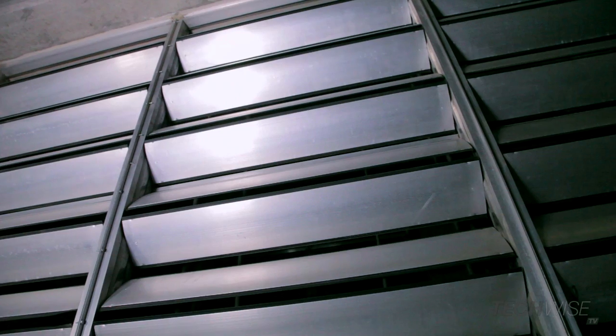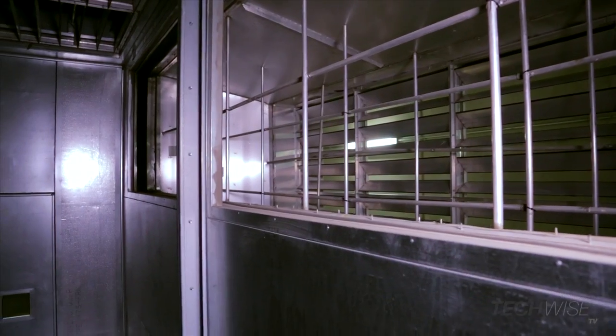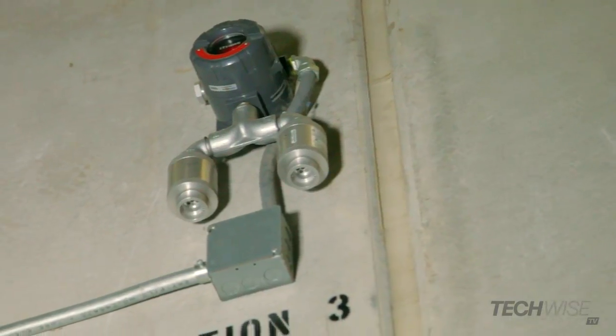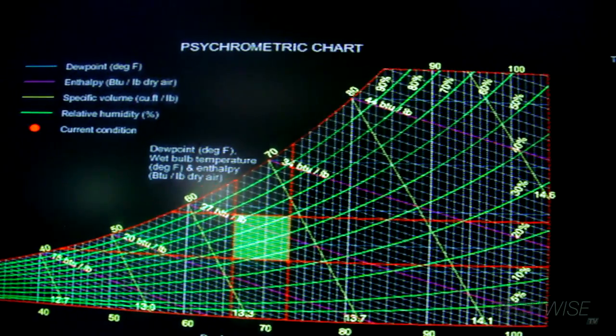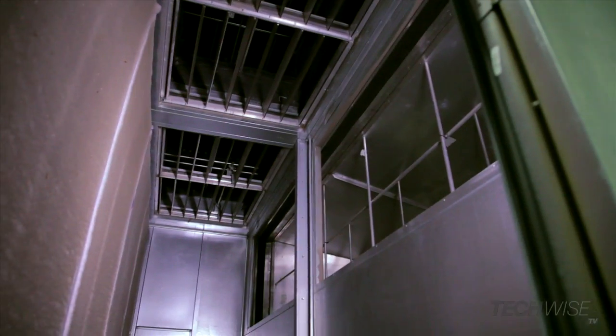We have louvered panels that back up to each of the air handlers that feed into our equipment. When our temperature sensors indicate that we're in this ideal cooling and humidity range, those panels will gradually open up, drawing that air in through each of the air handlers.